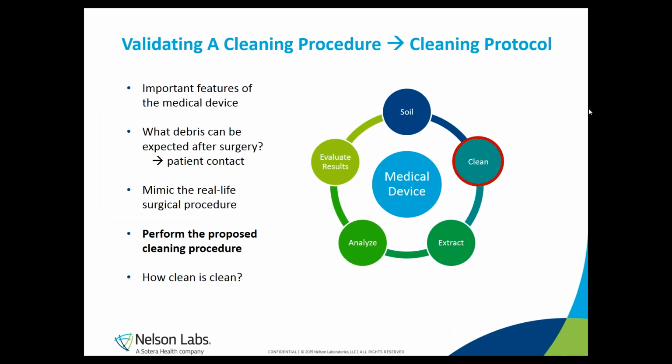After soiling, the reusable device in a representative scenario, a proposed cleaning procedure will be performed, and this cleaning procedure may be either based on a proposed instruction for use, a draft version that we get from our sponsor, or we can help you writing a protocol with our in-house experience.